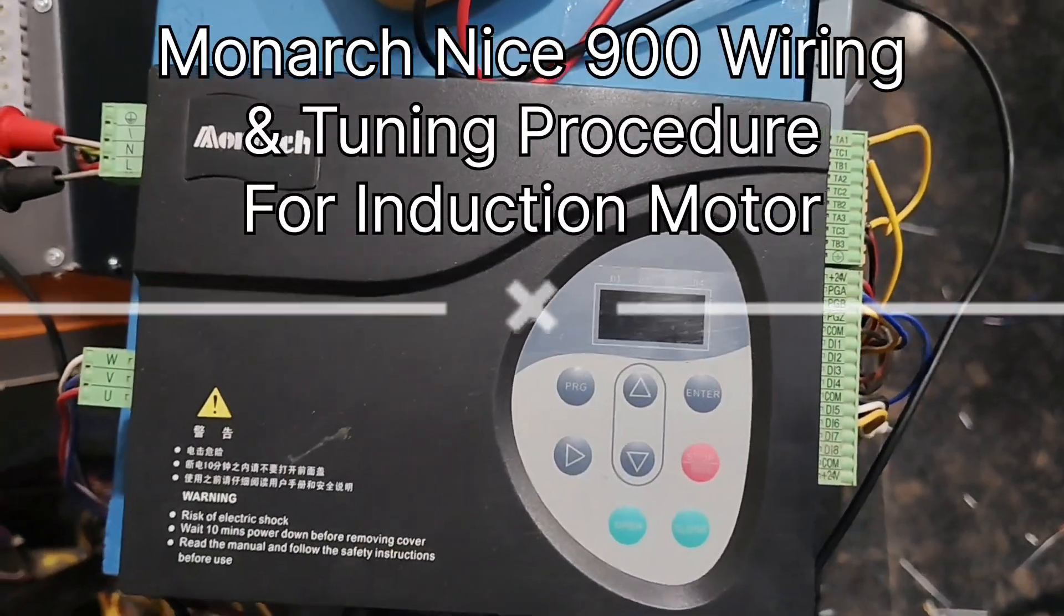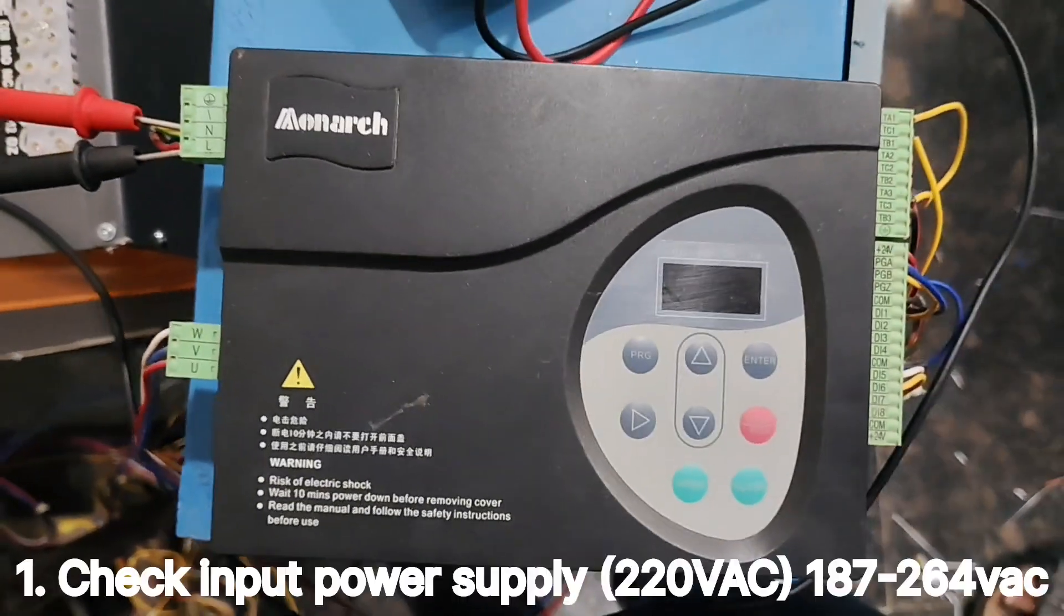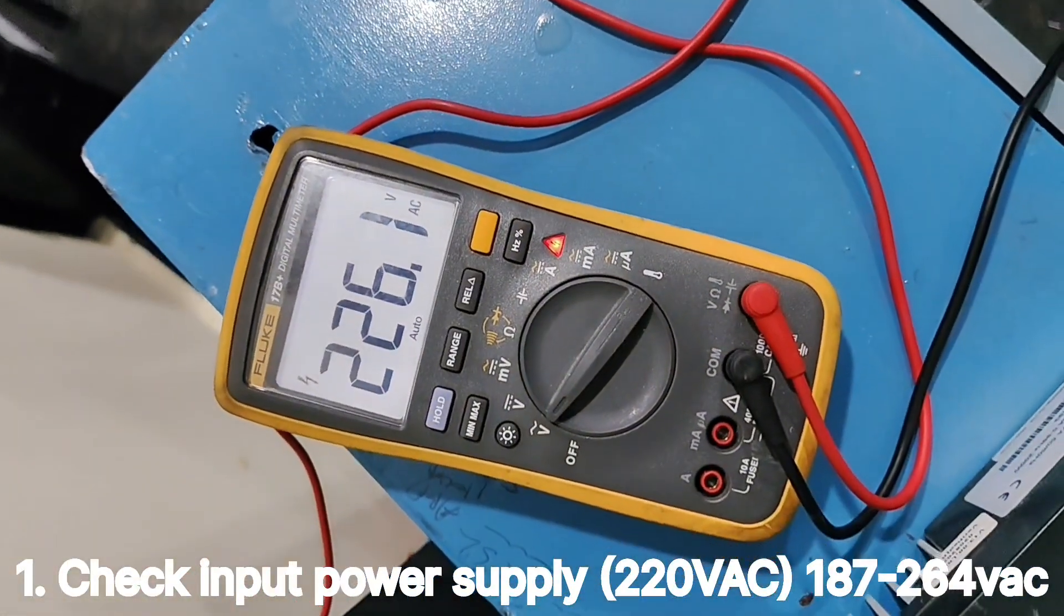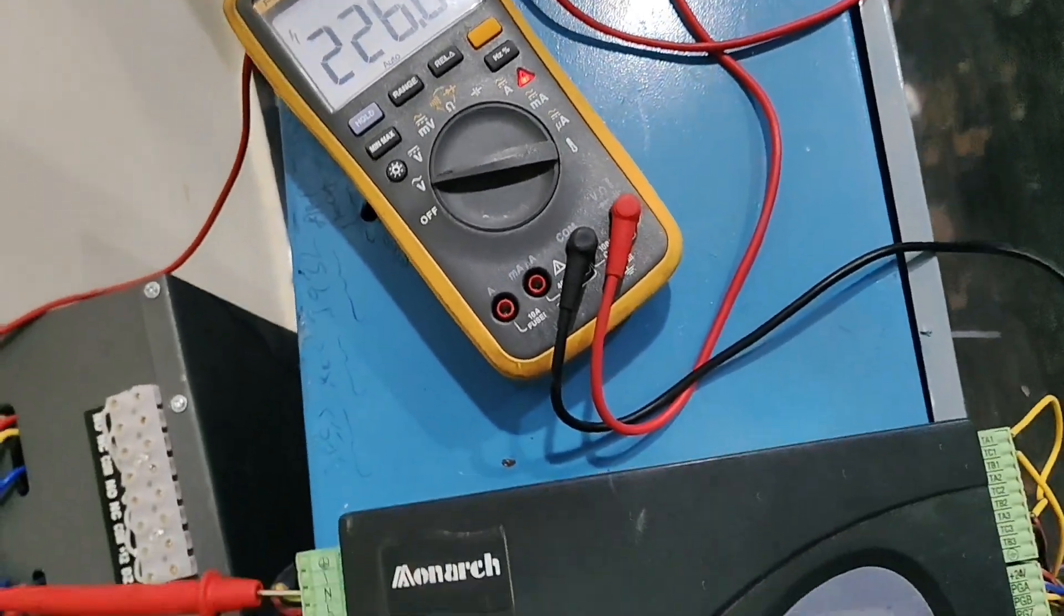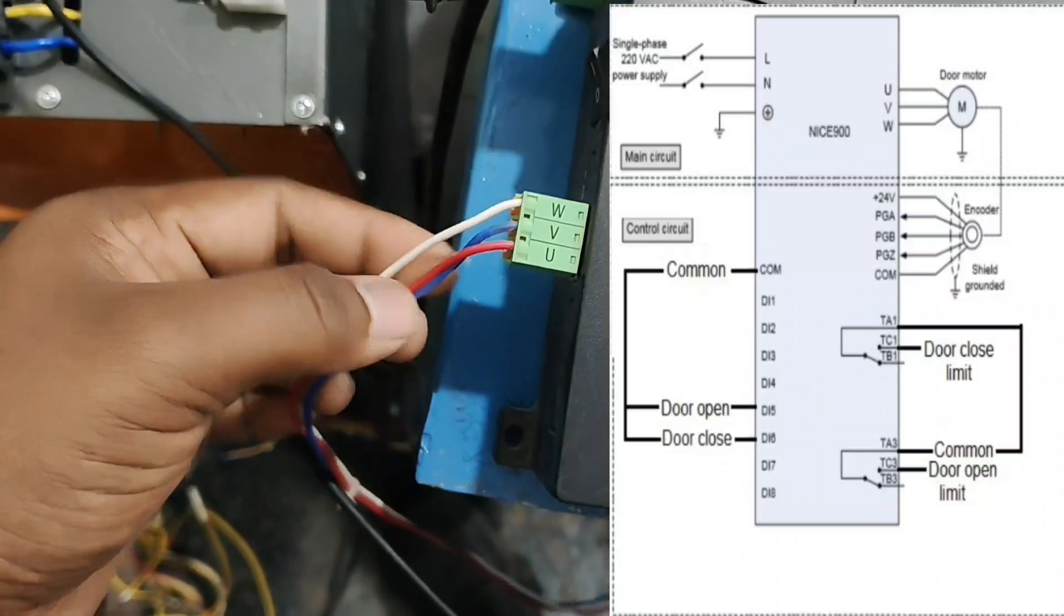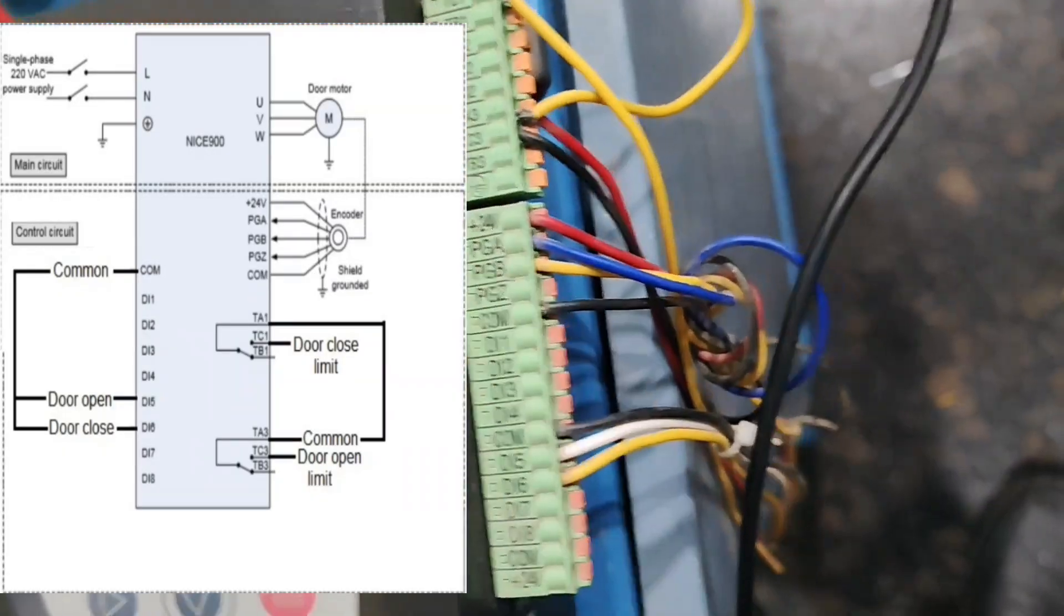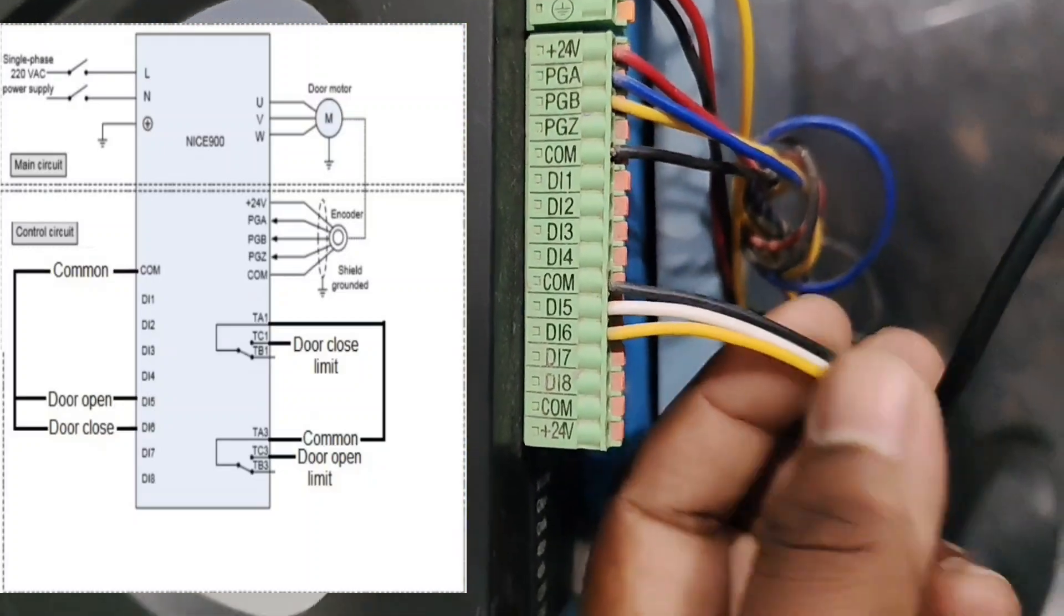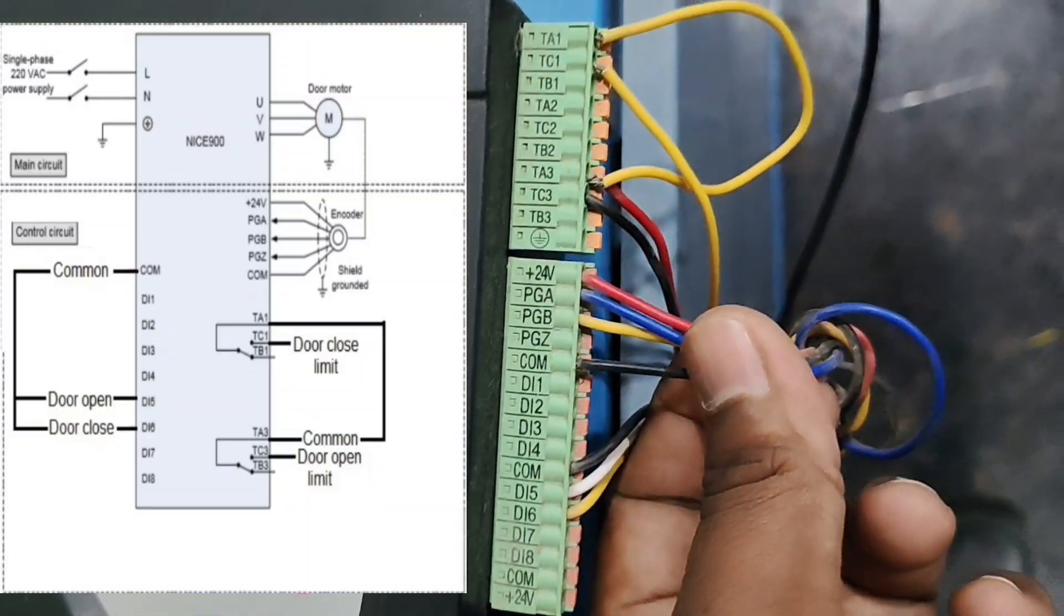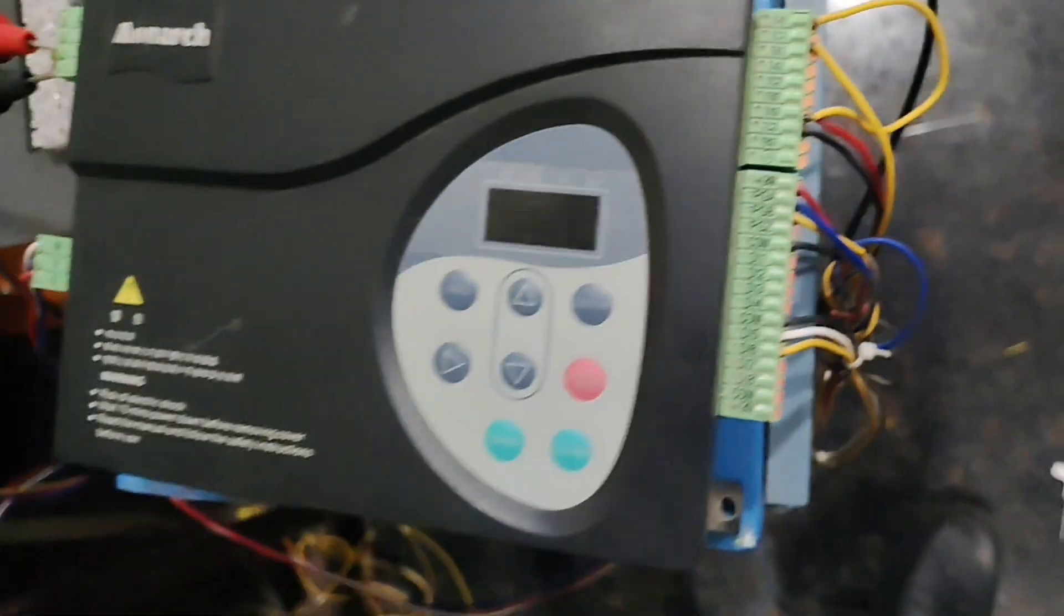Nice 900 programming and commissioning tuning procedure. First, check input voltage is 226V. After that, connect door motor wiring, door open close command and common wiring, door motor encoder wiring, and door open limit and door close limit wiring.